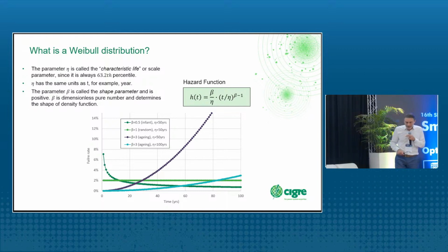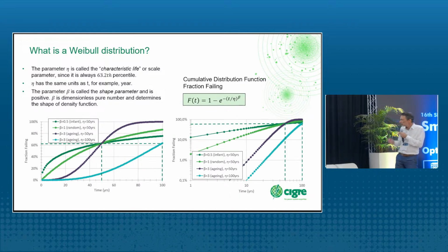Before I come back to the transformer, I have to explain a little bit more about the Weibull distribution. In the former graph, I showed the failure rate. Here, we are using the cumulative distribution function, also called CDF. And this CDF shows which fraction of the population failed already. So if we have here, for example, again, beta equals 3, and we say eta is 50 years.